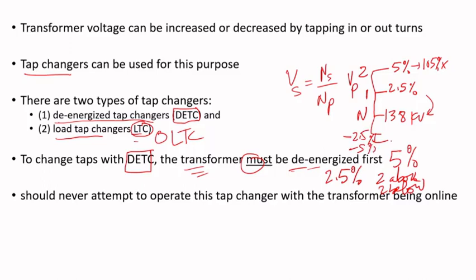You should never attempt to operate a de-energized tap changer while the transformer is energized. If the transformer is under voltage, you should not operate this tap changer, because you will damage the tap changer, could cause damage to the transformer, and personnel could be severely hurt. It's dangerous — you don't want to do that.